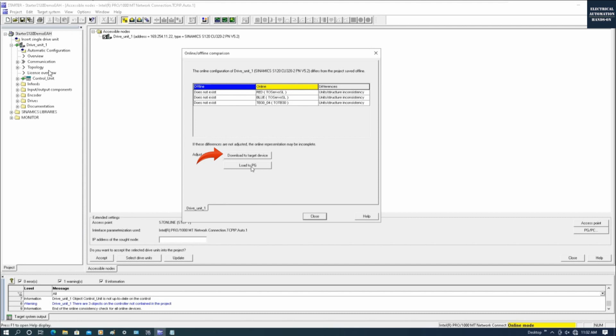Download the entire offline project to the online CU. Another way that I used to do, before I do something for this hardware, is to do the load project to PG to back up the online configuration, and then you can do something else. Load to PG means we will upload from the CU to the offline project. Basically, we could back up the online configuration from the online CU to our offline project and save as to other place, and then we're starting from scratch, reset factory mode and start over again, right?